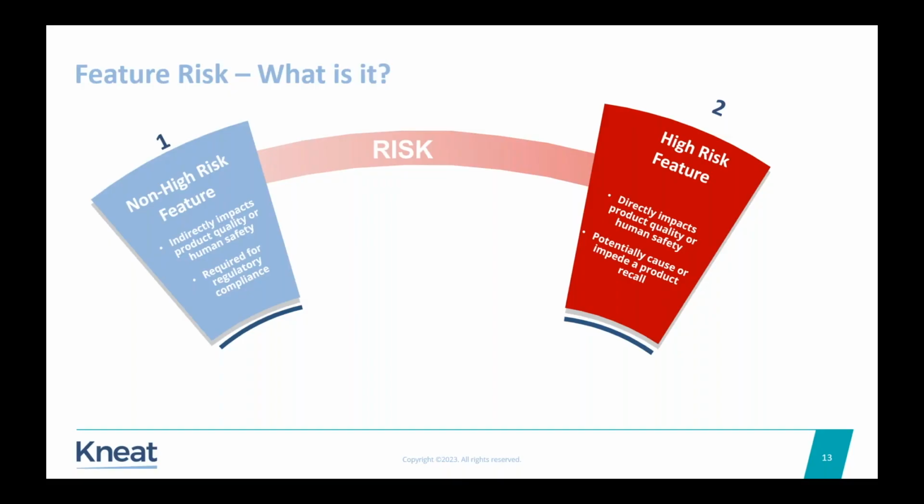So again, audit trails, they can be reviewed regularly, and we'd see those as more of a medium to low risk. But that's really what the FDA look at. It's going to be on a spectrum, but the FDA views it as kind of binary. So if you go on to the next one, now we'll look at a breakdown of the testing approaches that this new CSA guidance gives us.